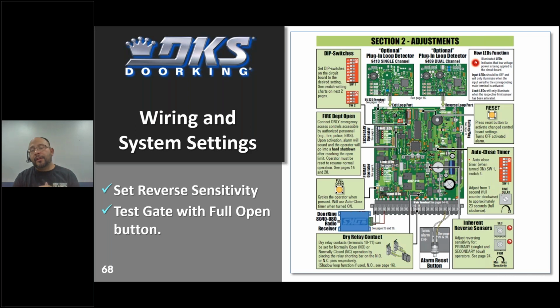And depending on the area you're in, you might have to adjust that a couple times a year, right? If you do see all 4 seasons, you at least want to do 2 adjustments a year, one for summer and one for winter, right? As we know, metal expands and contracts with the changing in temperature. So a setting for summertime may not work for winter time. And that's just a little potentiometer setting on the board.